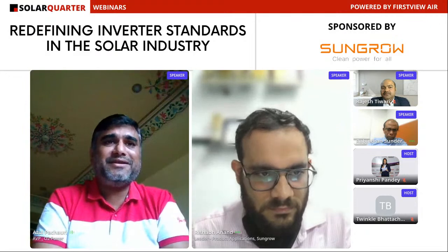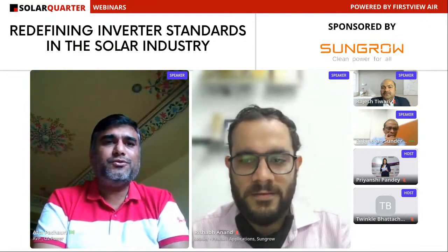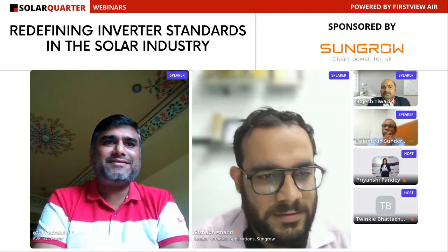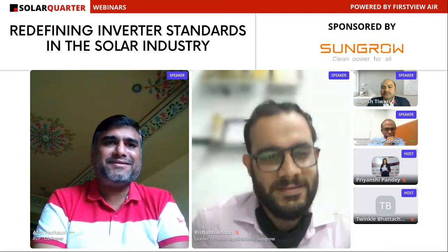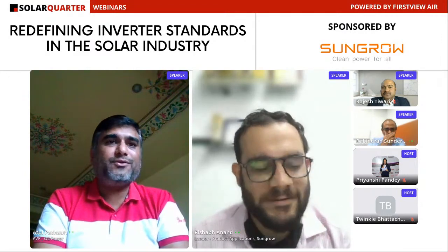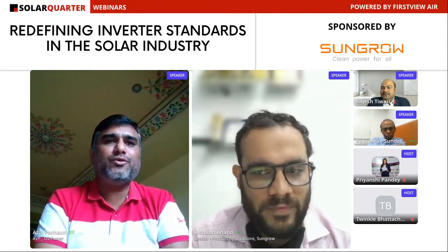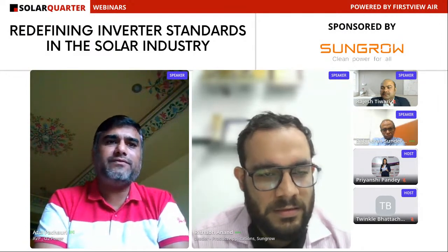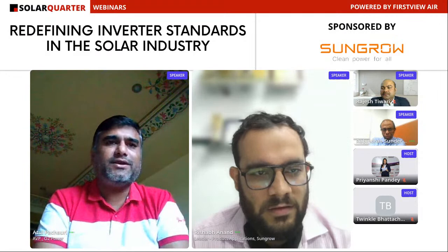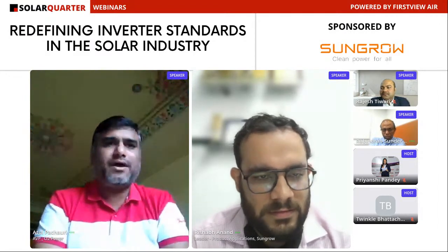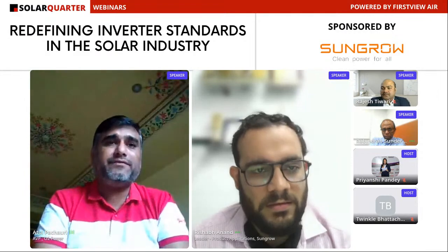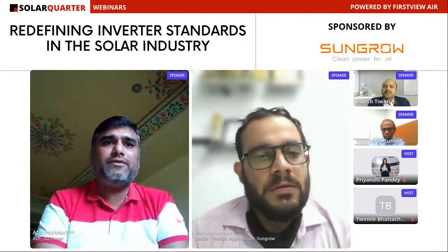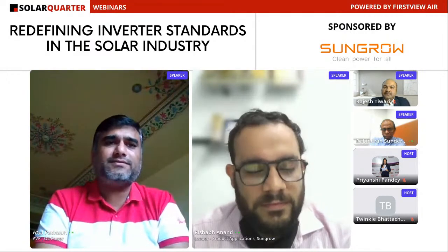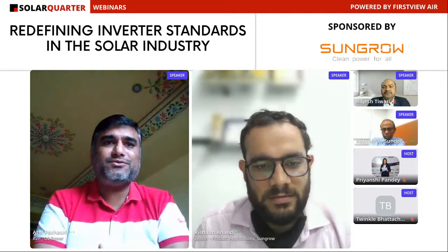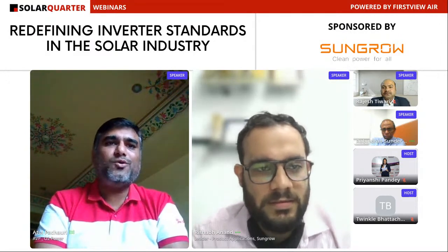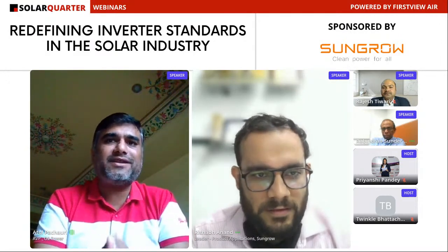This is again a very interesting thing for everybody to listen to, because I was behind the inverter suppliers to get rid of Modbus TCP/IP. So if SUNGROW is really interested in giving communication over IEC 104 or IEC 61850, then the messaging comes on that. 61850 as well as IEC 104 are both really versatile protocols, and definitely they will increase the speed of to-and-fro commands with the PPC or SCADA system. Very good. It's good for everybody that people are open to changing their protocols from Modbus to other faster acting protocols, right?